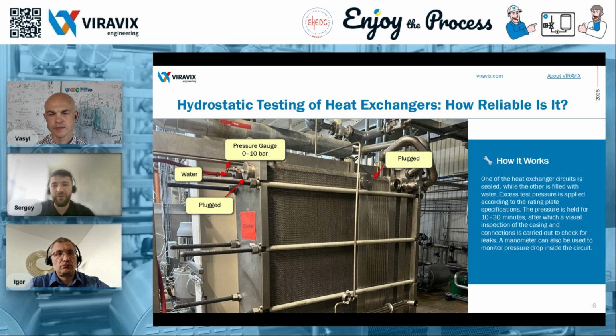One of the key advantages of this method is its simplicity and accessibility. It doesn't require any complex or specialized equipment. All you need is water and the heat exchanger itself. This method allows you to check not only for leaks, but also the structural integrity of the unit. It's suitable for heat exchangers of any size. However, this method has quite a few limitations. For example, it won't detect microcracks. Water only reveals large, visible leaks.